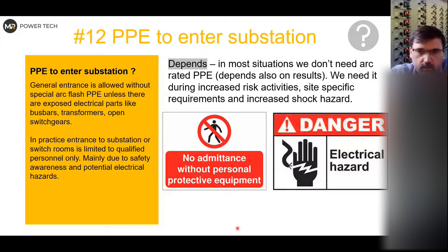And that's related to the situation when you go there, you start, okay, now I would like to do something, and you have to go back to take all your PPE and come back again to the substation, do your work, then go back to the office, drop the PPE. So typically, this is more a PPE strategy than real requirements. So I would say it depends really on the site-specific situation. I'm a fan of daily work clothes being up to 12 calories per square centimeter, because it fixes a lot of issues and makes it much easier to use. You get used to wearing this PPE because it is the same as normal clothing, and you are protected at the same time. And then we don't have this question of whether you need PPE to enter the substation or not, because you already have it.